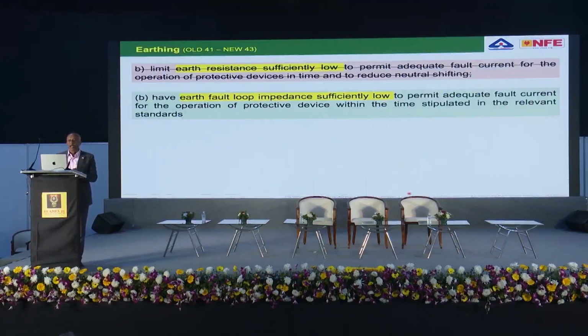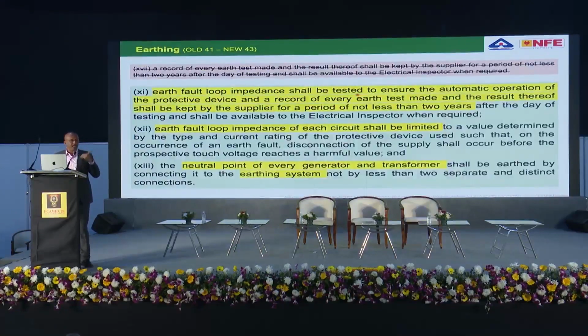Fault loop impedance, generally, if you look at the red one, which was the old regulation, limit earth resistance sufficiently low. So the old concept was, you have something in soil and you have an electrode. Now if you reduce the resistance of this electrode, you will achieve something. This earth electrode resistance has been removed in the standard a few decades back, very old, and in the regulation also it has now been changed. The earth fault loop impedance came into the picture, and a lot of changes like this have happened in the regulation.